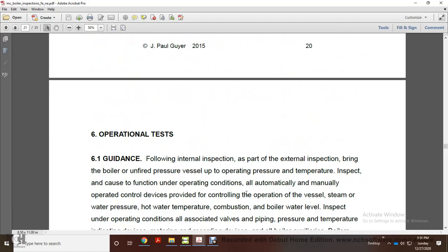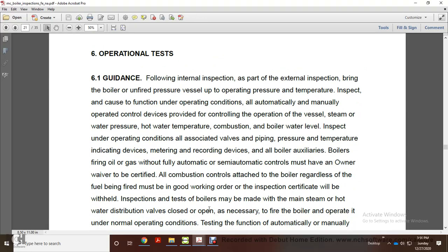Alright, 6. Operational tests. Guidance. The following inspection comes with the external inspection: bring the boiler or unfired pressure vessel up to the operating pressure and temperature, and inspect the function under operating conditions. Automatically and manually operate the control devices. Check the controlling and operating vessel steam pressure, hot water temperature, combustion, boiler water level, and under operating conditions all of the associated valves and piping, pressure, temperature, gauging devices, metering, recording devices, and auxiliary equipment.